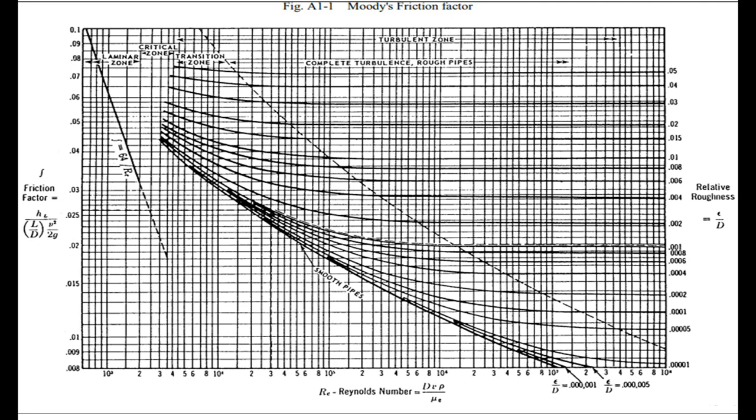This is the Moody friction chart. On the right y-axis you can see the relative roughness, and on the x-axis there is the Reynolds number. Using these two values in combination, you find the friction factor, which is used in the calculation of pressure drop for the pipeline sizing.